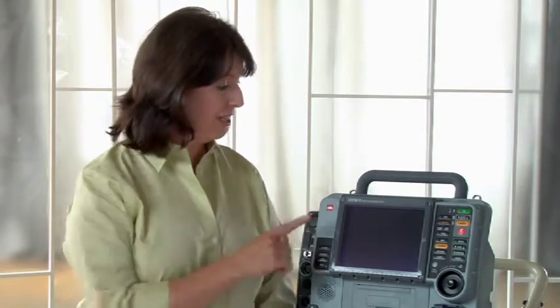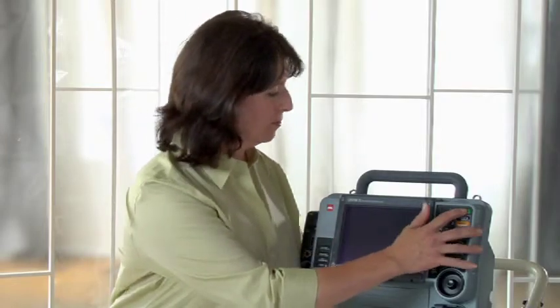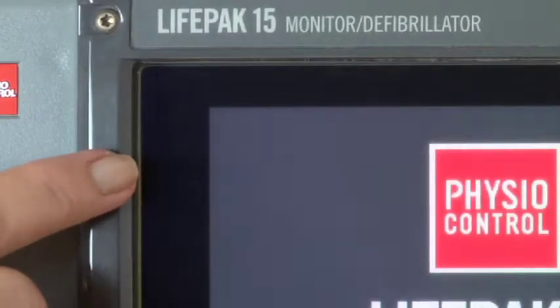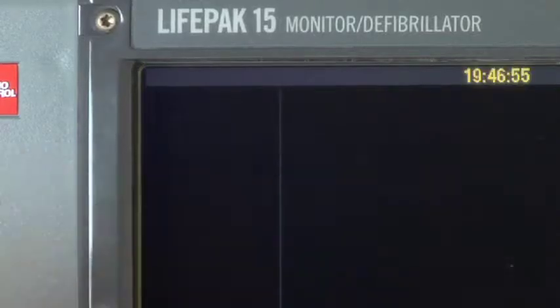The first is to watch the screen closely when you power on the 15. All the vital sign capabilities display briefly. Watch the SpO2 display area here closely during startup. There. This 15 can do all three. If it were only capable of SpO2, you would have seen only SpO2 during that flash.